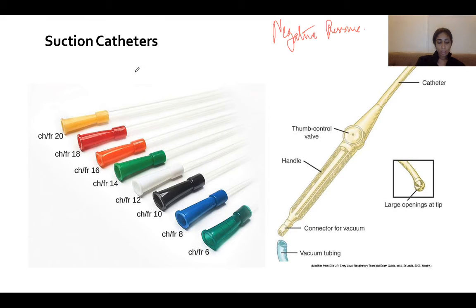Then vacuum regulator and gauge. A vacuum regulator allows one to operate and control the maximum negative pressure at the inlet of the suction apparatus. There is usually a gauge to indicate the pressure on the patient side of the regulator. Now, this will be the pipeline vacuum. From there it comes to a trap bottle and a regulator, right? From here, tubings go to which we attach the suction catheter. So the suction catheters are attached to these connectors, and this is used in the patient.